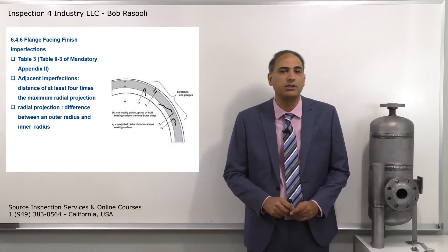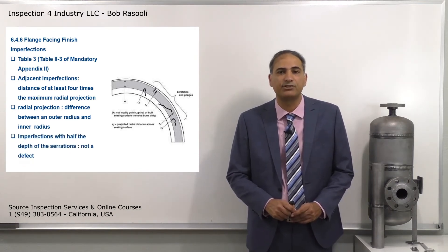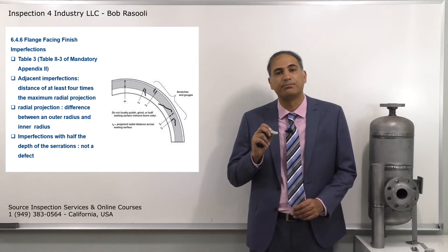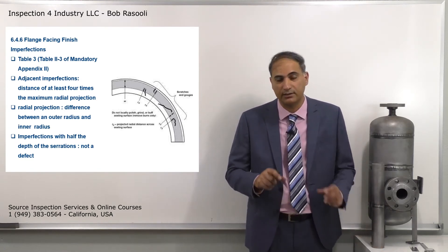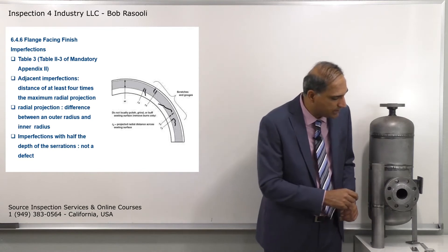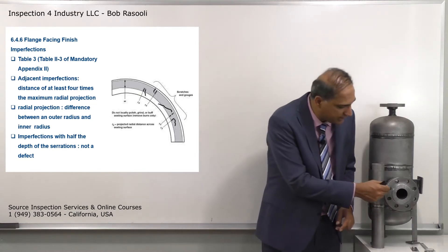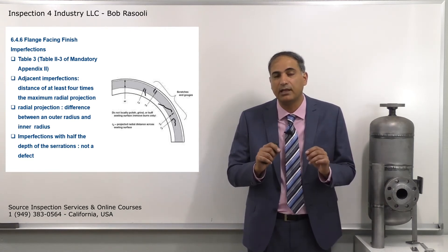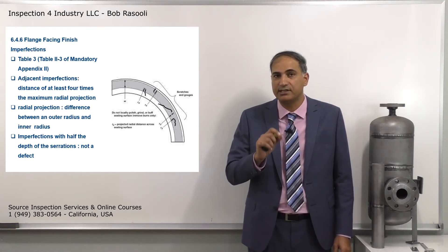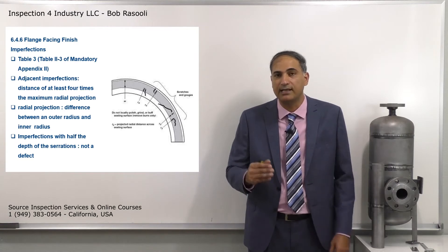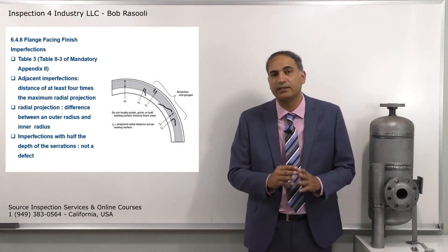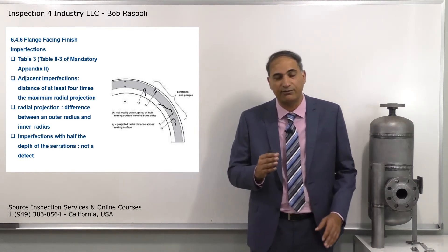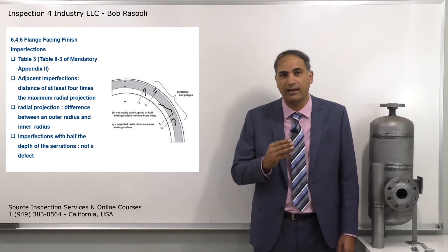The next key item is that an imperfection with a depth less than half the depth of the serration is not considered a defect, as addressed in 6.4.6. If you evaluate a scratch or cut and determine its depth is less than half the serration depth, you can ignore it - it's an imperfection, not a defect. You can only consider rejection when the depth exceeds half the serration depth.